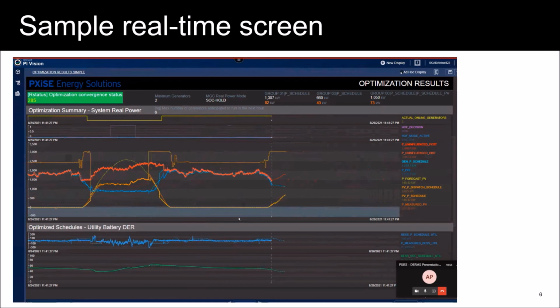But there are times during the day when the generators can be turned entirely off. There's a small rectangle just below the top trend that tells operators that anytime in that window, all the generators can be turned off and the system can run on 100% renewable power. We've demonstrated that now for several months. It's quite a feat to have the system determine when it's safe to go with 100% renewables - no inertia is in the system now. It's controlled with zero inertia, using the utility battery and the customer DERs.